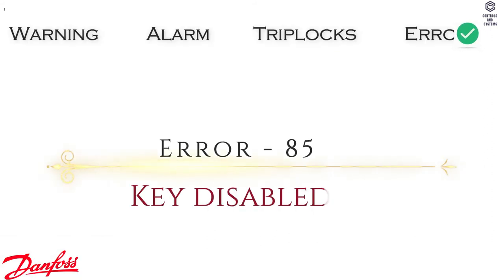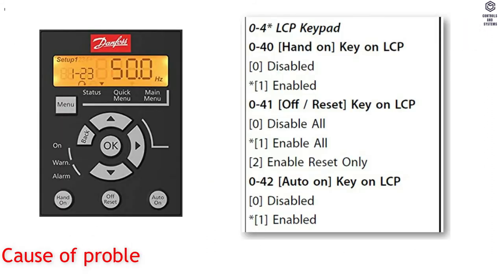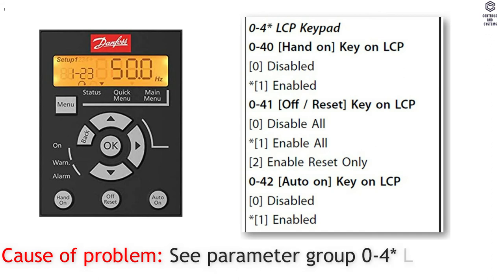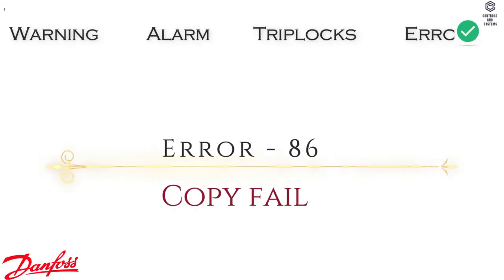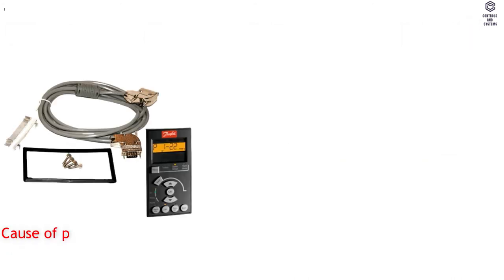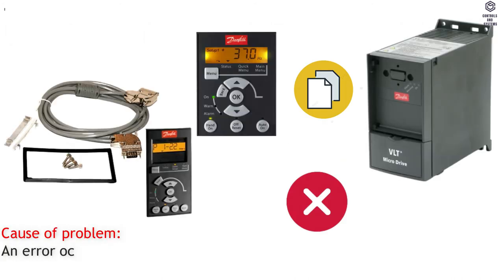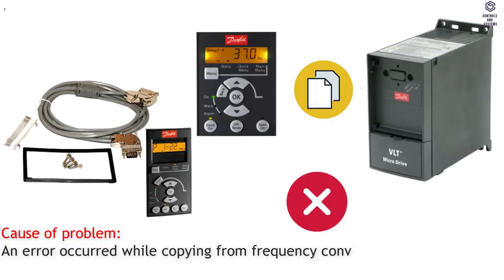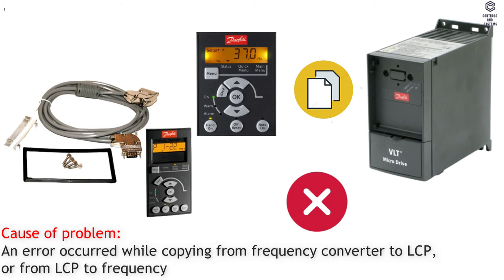Error 85: Key Disabled. Cause of Problem — see Parameter Group 04 LCP. Error 86: Copy Fail. Cause of Problem — an error occurred while copying from frequency converter to LCP, or from LCP to frequency converter.